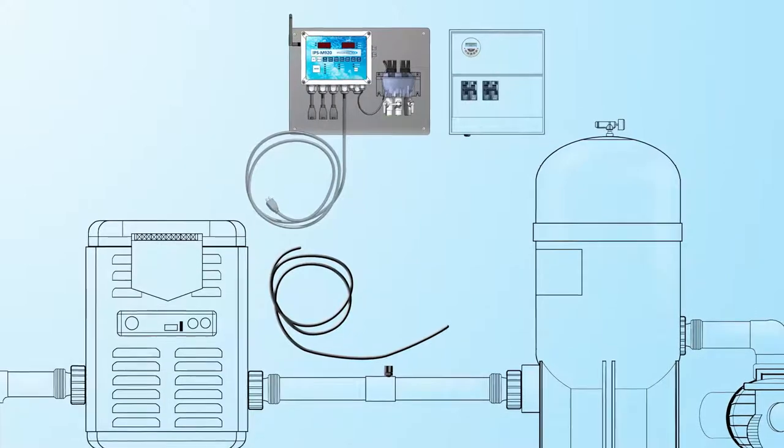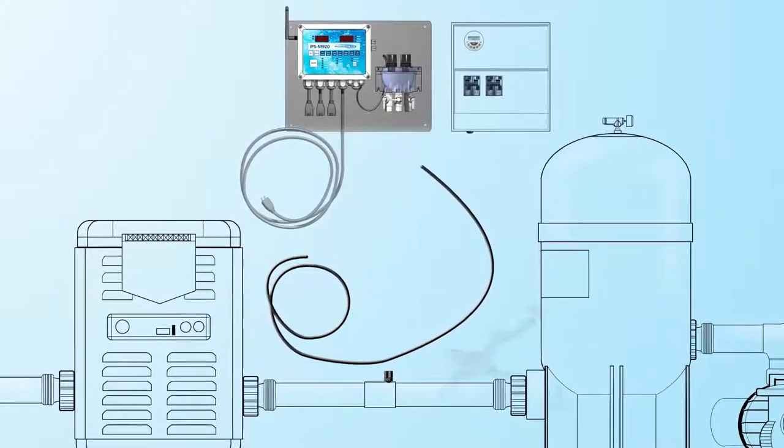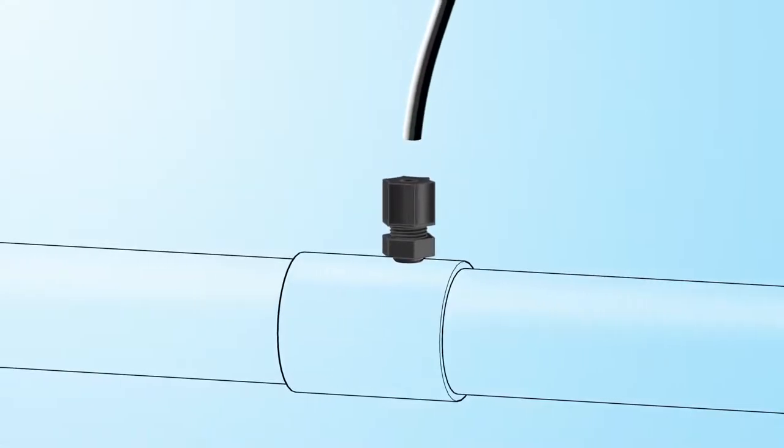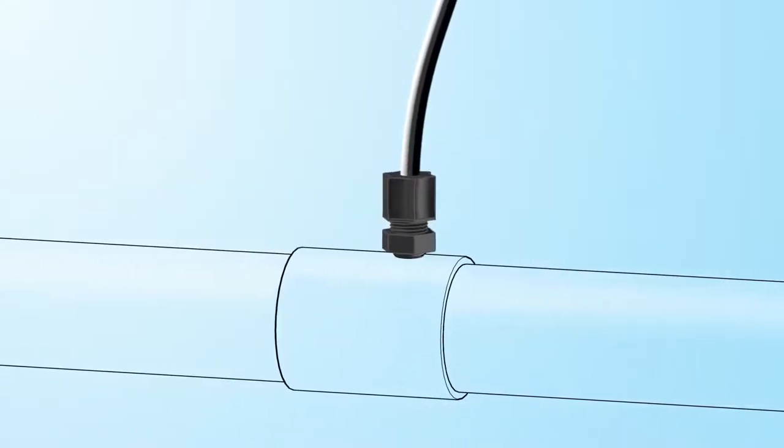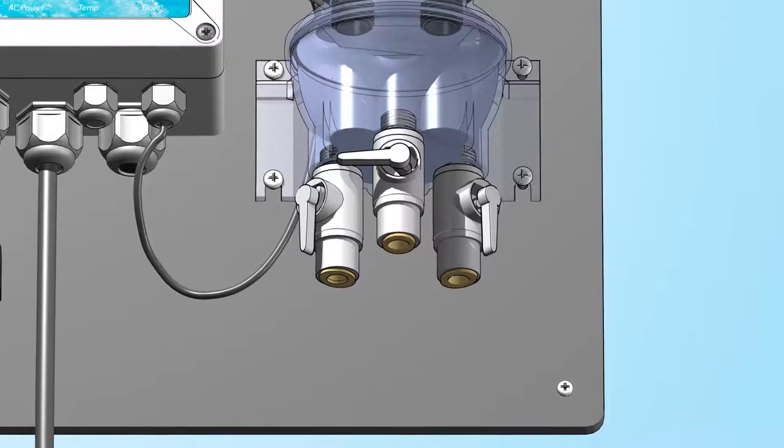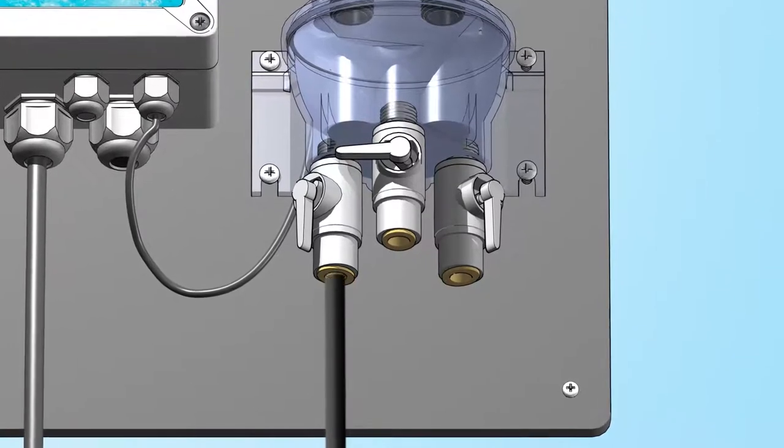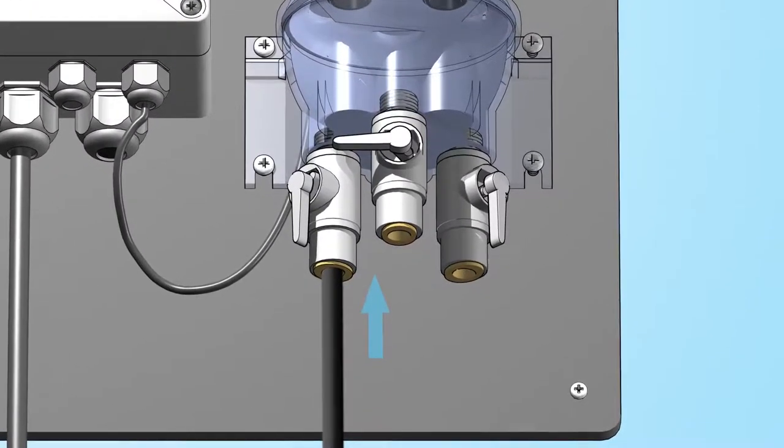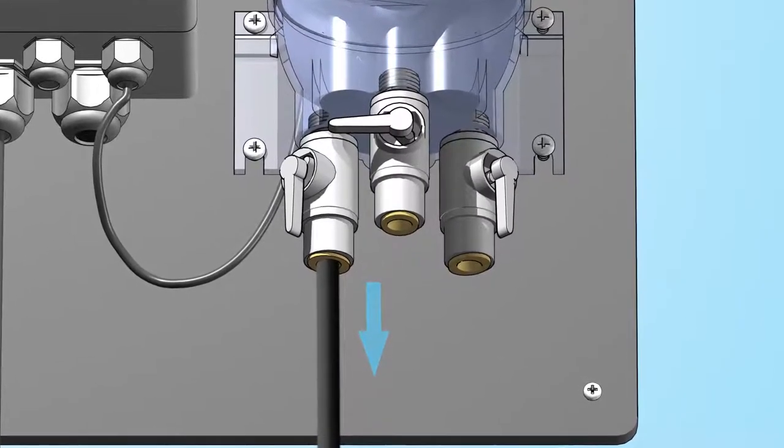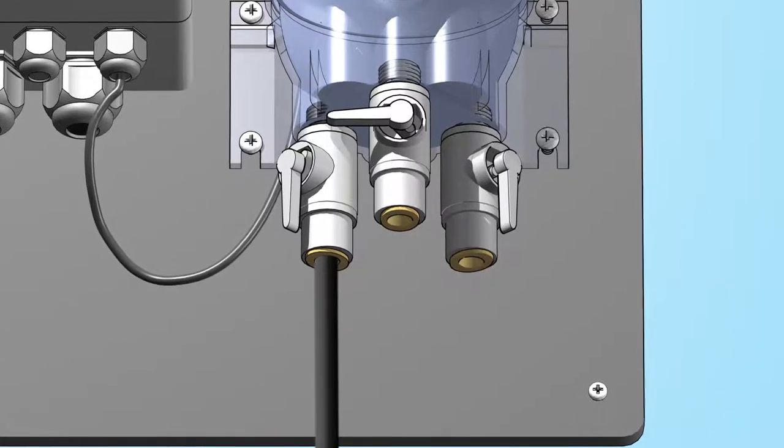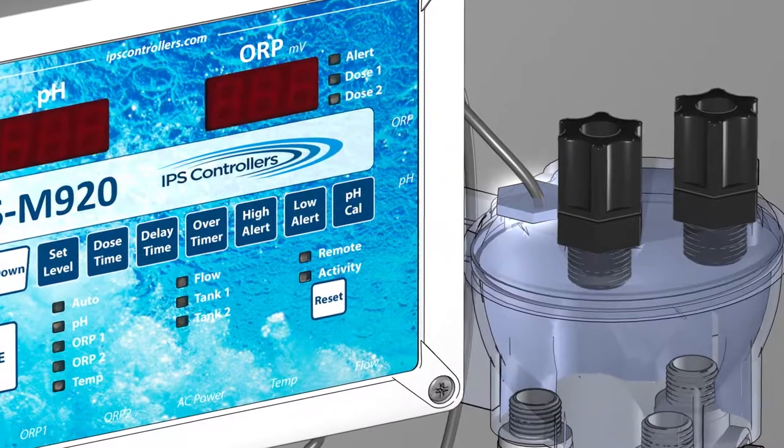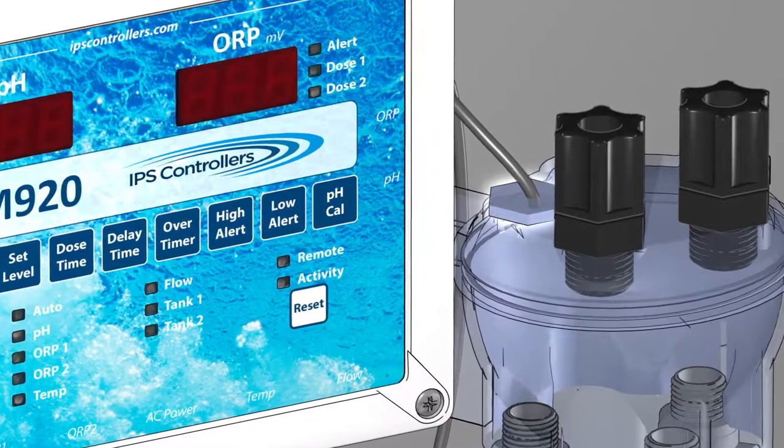Measure a length of tubing long enough to allow easy routing from the pipe fitting to the flow cell. Insert one end of the tubing into the compression fitting and hand tighten the nut to secure the tubing. Insert the other end of the tubing into the valve on the far left of the flow cell. Push the tubing into the valve as far as possible and pull back slightly. This will lock the tubing in place. This port contains an integrated flow switch that will prevent chemicals from feeding into the system when the system is off.